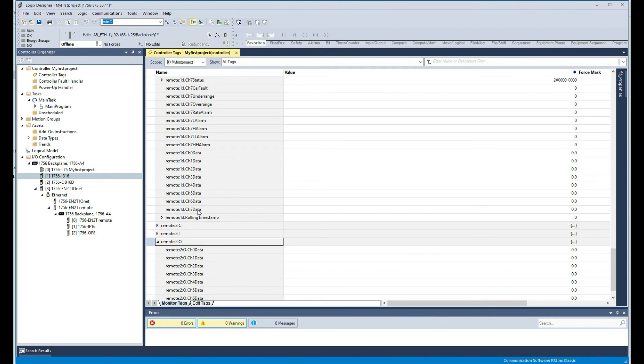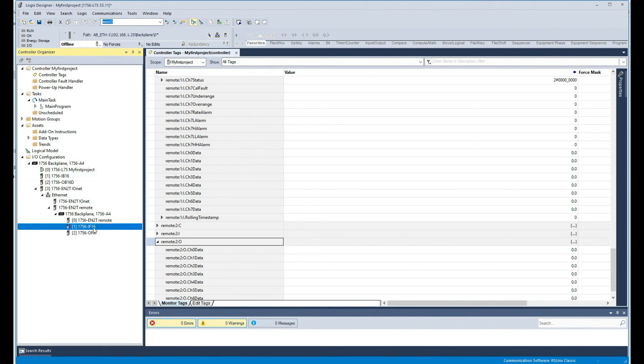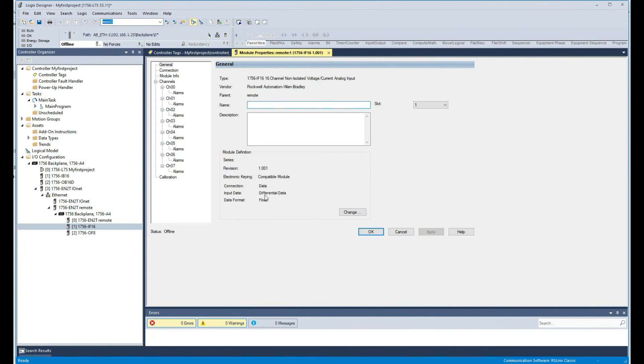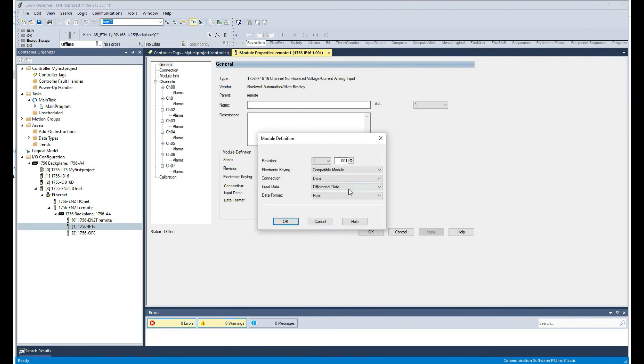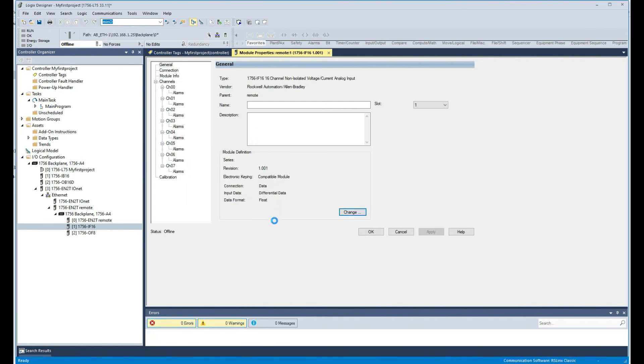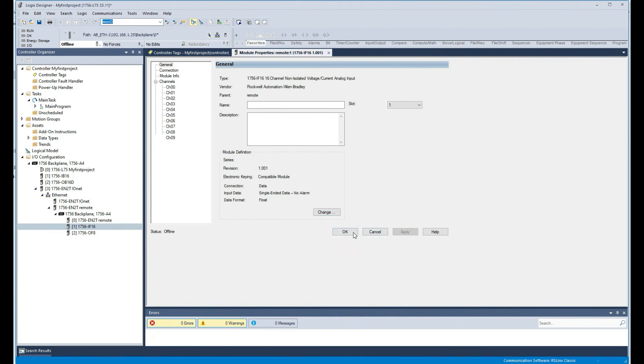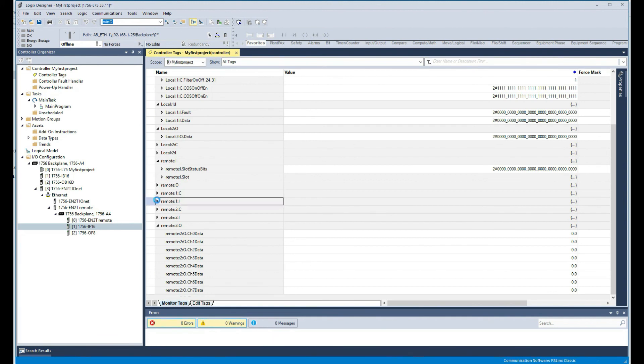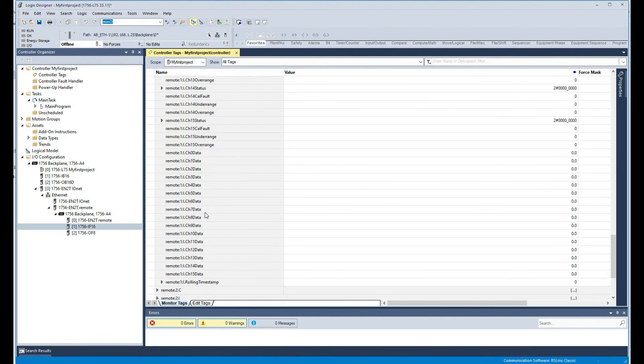I want to quickly mention — if you notice we only have 8 channels, but the module is an IF16 which supports 16 channels. The reason is that by default the settings use differential mode rather than single-ended, and with differential you only get 8 channels. If you want 16 channels, you can come here and select single-ended data — or single-ended data with no alarms — as a float, then click OK and Yes. You'll notice we now have 16 channels instead of 8.